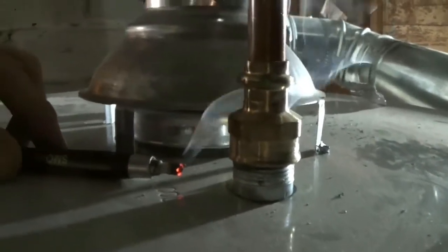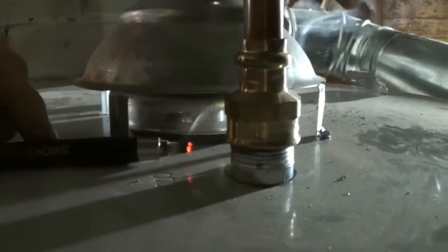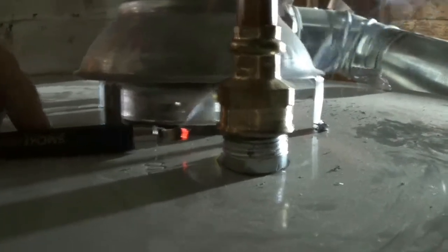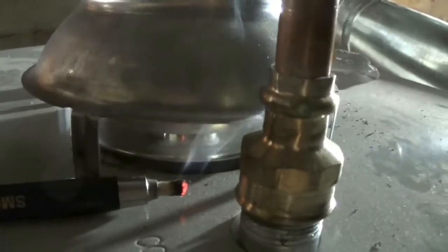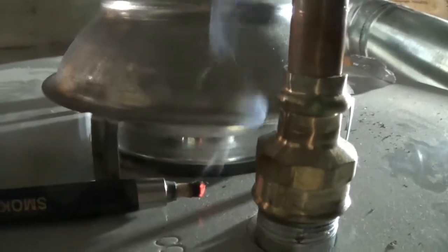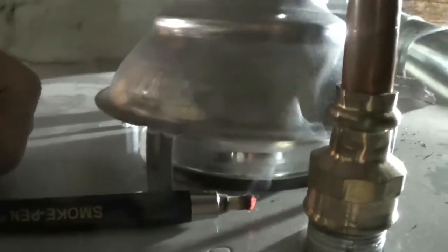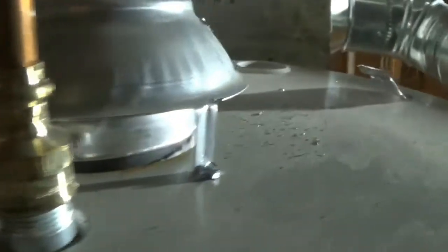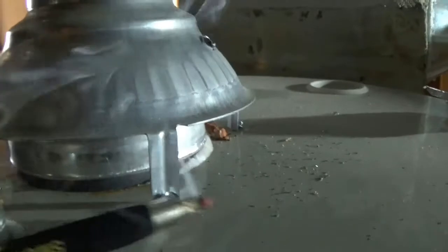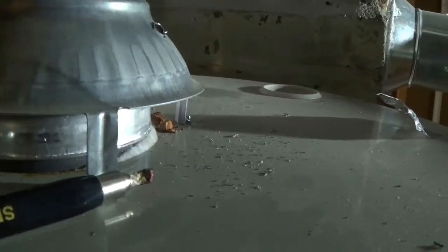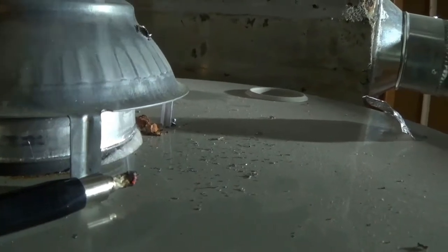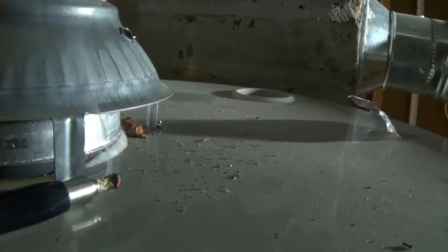How far away do you need to have it? I like to, if I can, have it right underneath where it's right on the dividing line. So it's either going truly one way or the other, right? And it's wavering back and forth. It's kind of looking like it might start to pass, but it's really close to 60 seconds, right? So it's not getting pulled in, it's just moving straight up sideways next to that draft hood. It's not being pulled in, and now it's been 60 seconds.